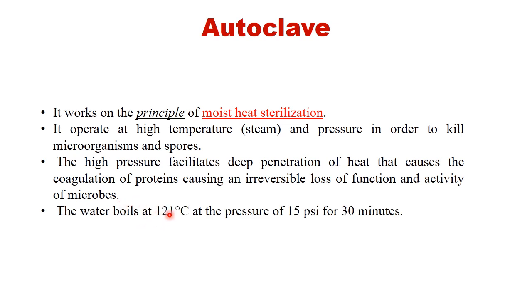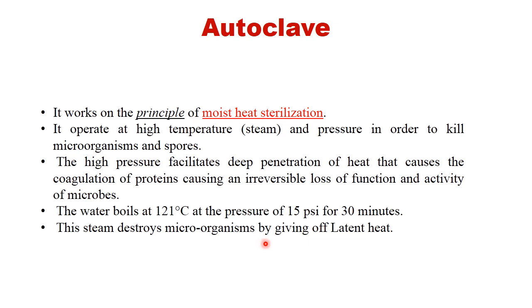The water boils at 121 degrees centigrade at the pressure of 15 pounds per square inch for 30 minutes, and that steam is used for sterilization of articles. So, autoclave requires water that needs to be converted to steam at a high pressure, and that steam is used for sterilization. This steam destroys the microorganisms and spores by giving off latent heat. If you recall our basic physics of school days, we have seen that steam causes more thermal burn or injury in comparison to water because it has higher content of latent heat.